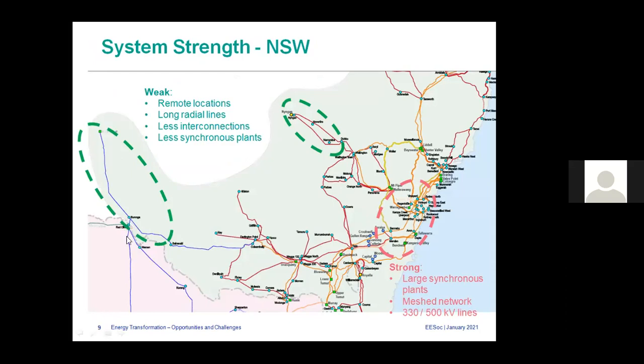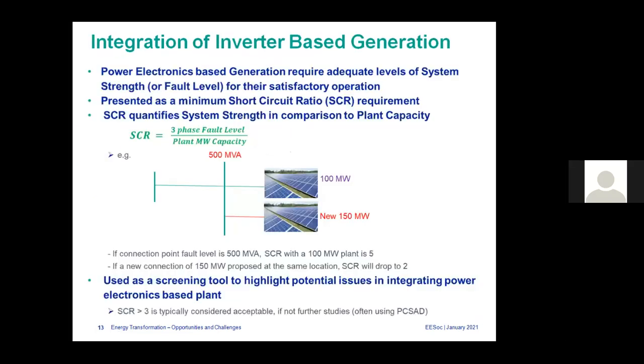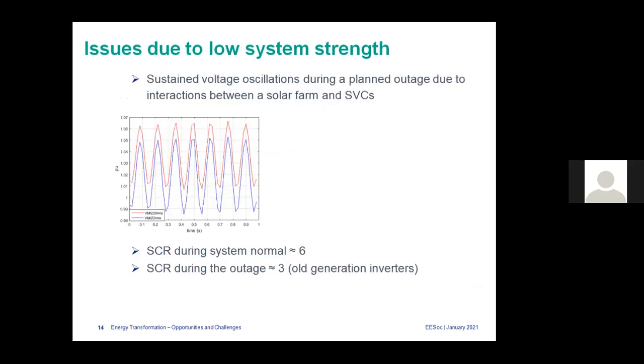Then what we noted is there were oscillations. In fact, we haven't modeled this. When this incident happened about 4 years ago, we didn't do any PSCAD modeling for these kinds of operational or even connection studies. But people working at the substation noted some flicker, lights flickering. Then they called the control room and told them there is a problem, and they noted voltage oscillations happening in the system. Because there is an SVC and a solar farm at Broken Hill, they were interacting with each other and causing this oscillation. It's about an 8 Hertz oscillation because of that low system strength situation.